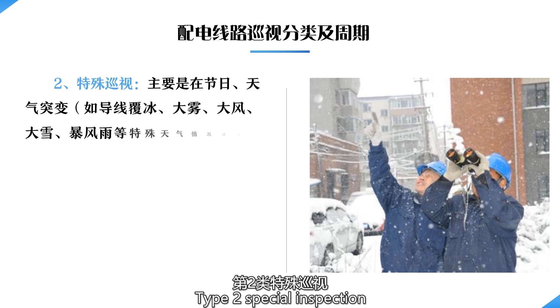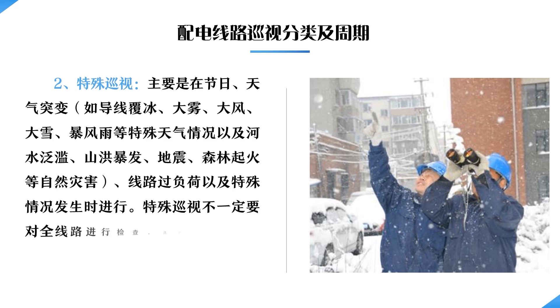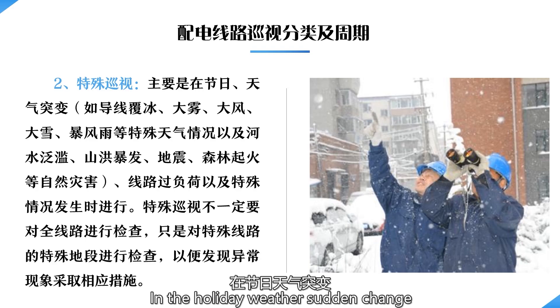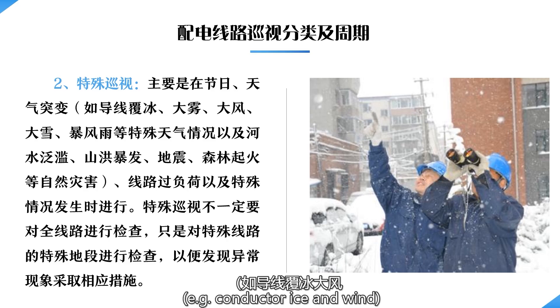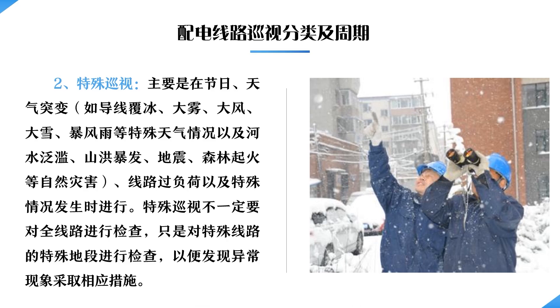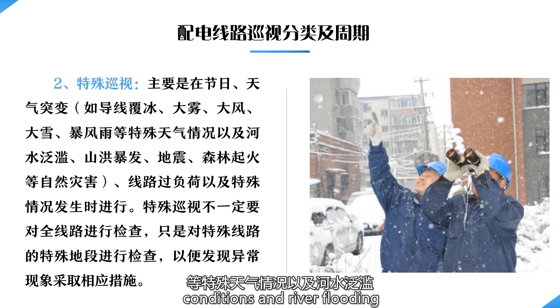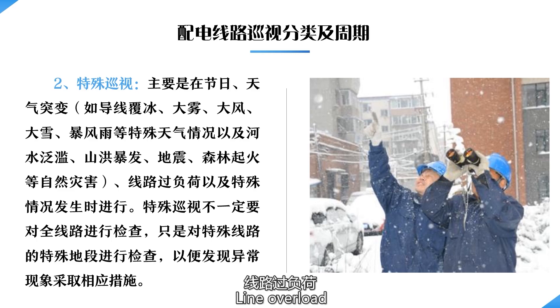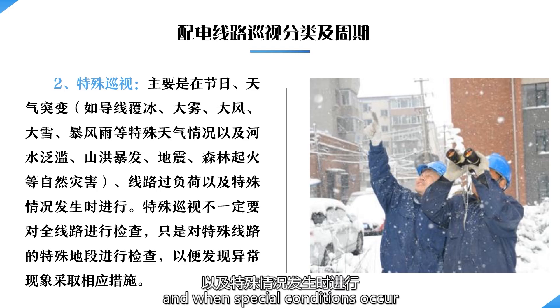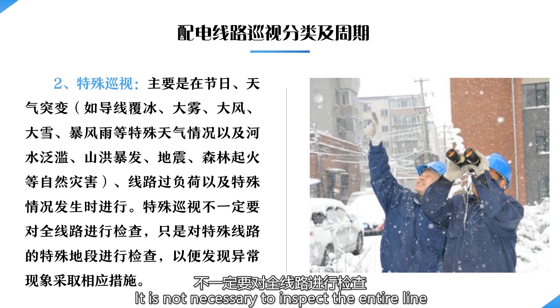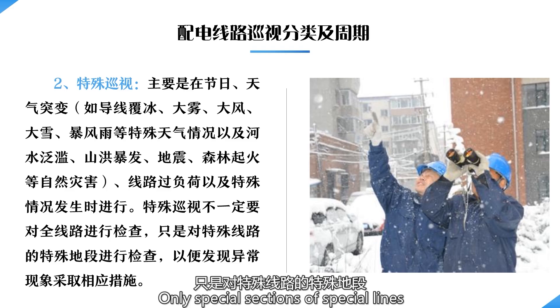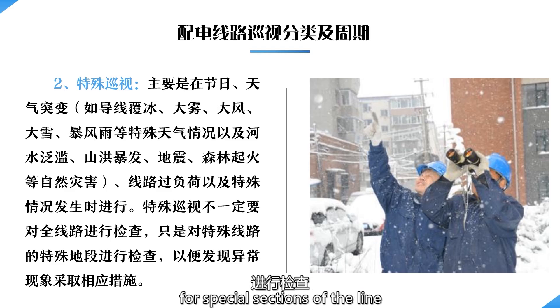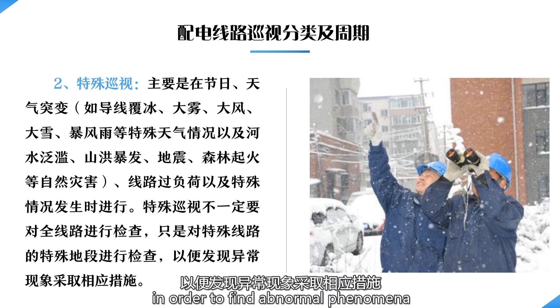Type 2 is special inspection. Special inspection is mainly carried out during holidays, after sudden weather changes — such as conductor ice and wind — and other special weather conditions, as well as during river flooding, natural disasters such as forest fires, line overloads, and other special conditions. It is not necessary to inspect the entire line; only special sections are inspected in order to find abnormal phenomena and take appropriate measures.